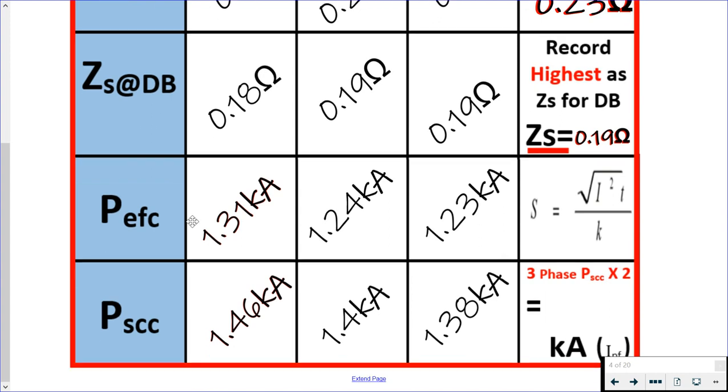Looking at our prospective earth fault current, we have 1.31 kilo amps measured, and that 1.31 kilo amps, this is where we're going to be utilizing it. We're going to be using it in this adiabatic equation to make sure that our protective conductor is the right size in order to meet what's called the thermal constraints, to make sure we're not going to damage that insulation under fault conditions.